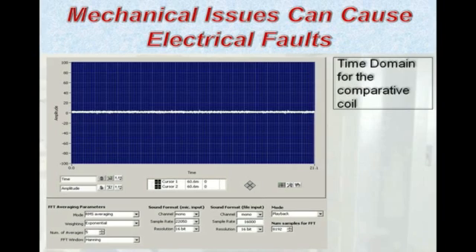On the sister unit that was sitting adjacent, you can see clearly there are no deviations from the instrument noise, which indicates the complete lack of any type of discharge, mechanical vibration, or loose components within that unit. This is what one would expect on a properly functioning device.